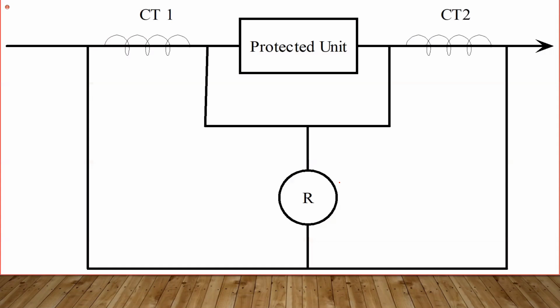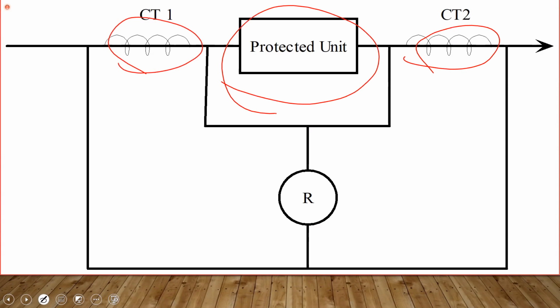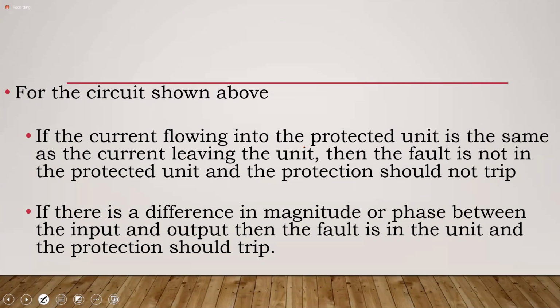All right. And in terms of basic setup, this is what you have. You have your CT on one side, CT on the other side. This is what you are protecting, so that's the piece of equipment you are protecting. And this is our differential relay. We're not going to get into any math with this, but the principle is that the current flowing into the protected unit must be the same as the current leaving. If the current entering is equal to the current leaving, then it means that the fault is outside of the equipment that you are protecting, and therefore it should not trip. If there's a difference between the current coming in and the current leaving, then the fault is on the unit and it should trip.